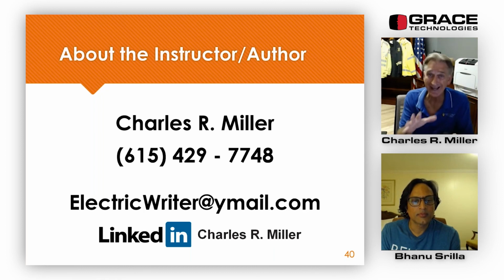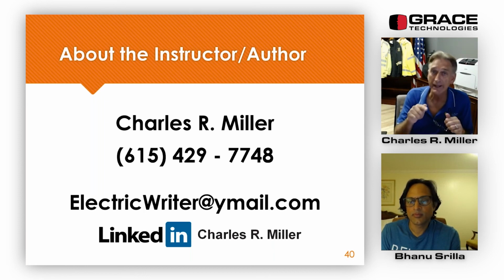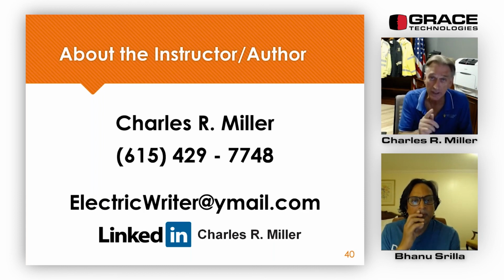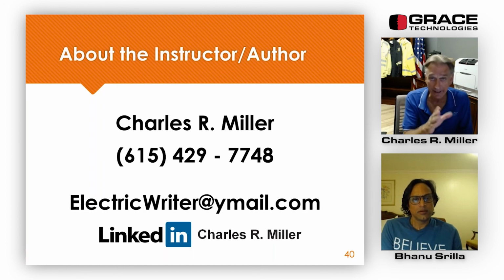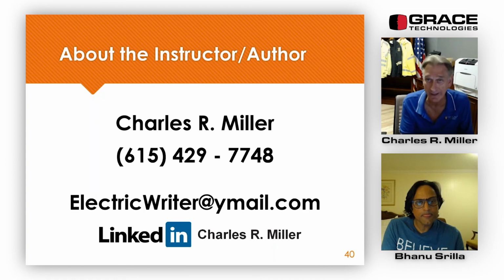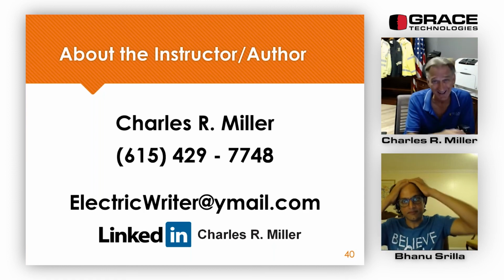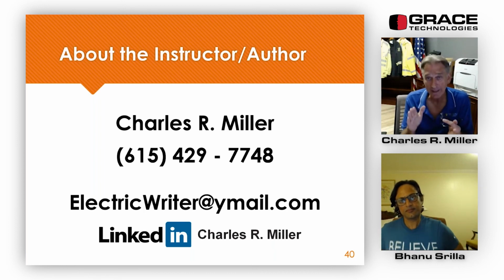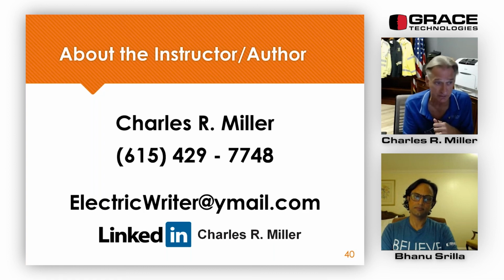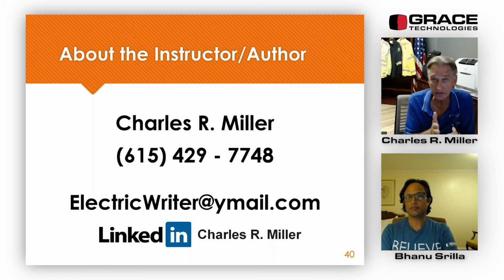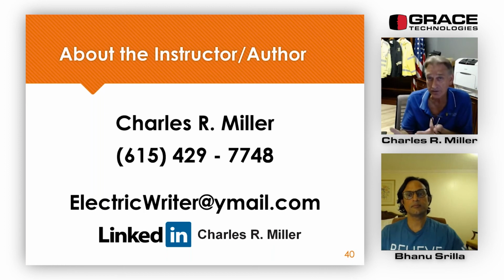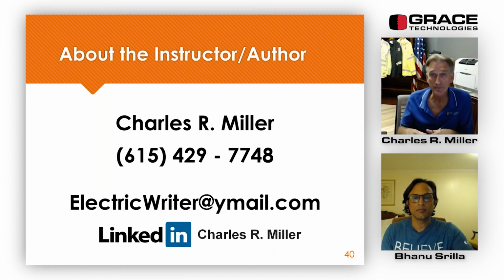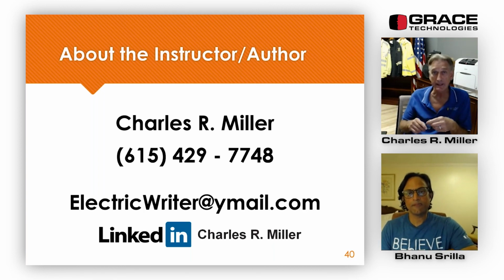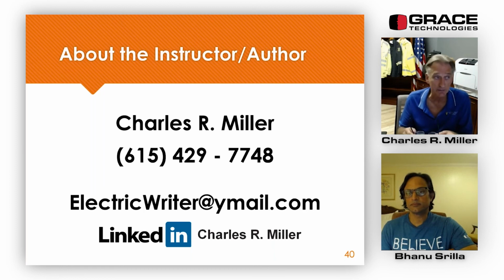We did hands-on training on a 3-phase delta corner-grounded system. I've known about this forever from schooling, but I had never seen this system. Since then, I've shown a lot of pictures and put them on LinkedIn. Evidently, Kansas City, Kansas has these systems around their area. A corner-grounded delta system has a conductor on the neutral that had white tape on it, and it was a hot conductor, but it is also intentionally grounded. So it really comes back to the point: is someone a qualified person to work on this system? Do they know what voltages are coming into this cabinet, to this device? Do they know what they're testing for, phase to phase and phase to ground or phase to neutral? All of that should be part of being a qualified person, knowing what this particular system is.